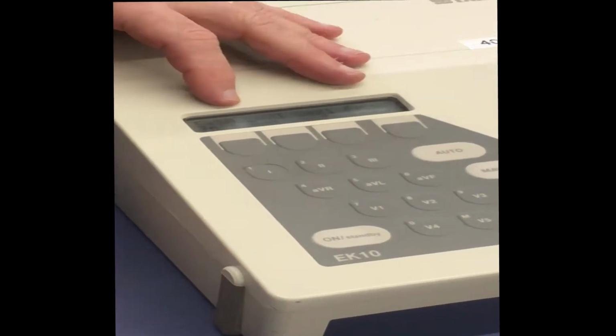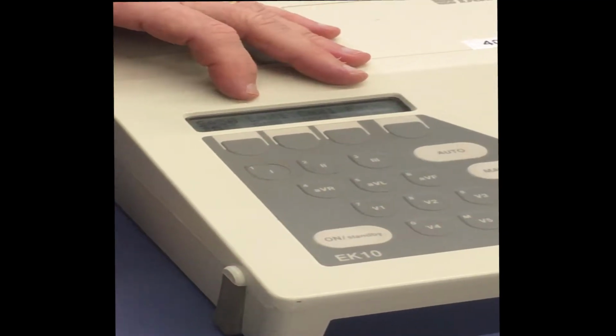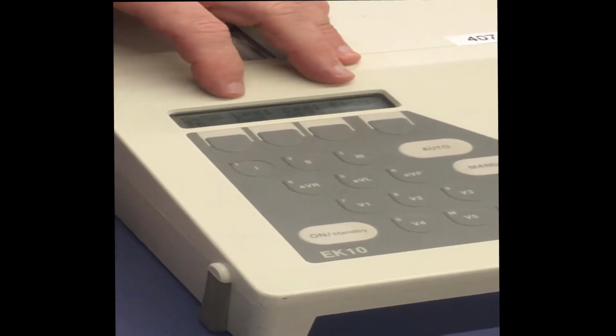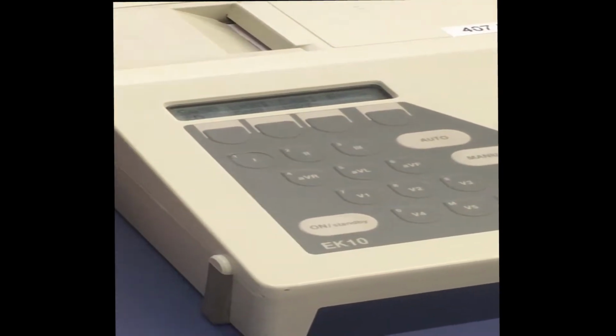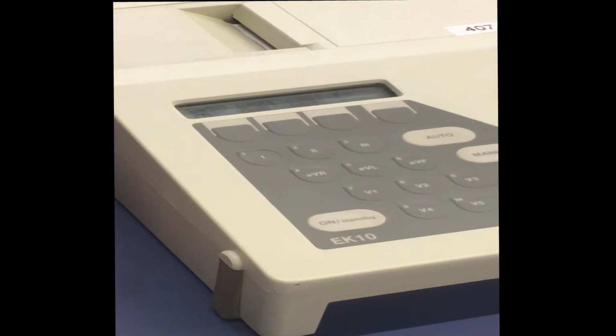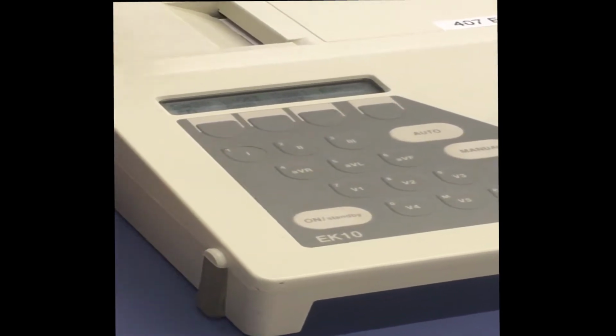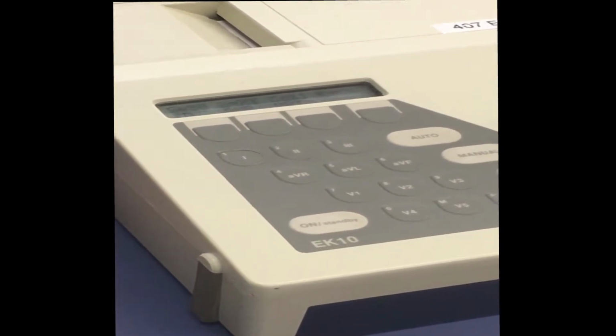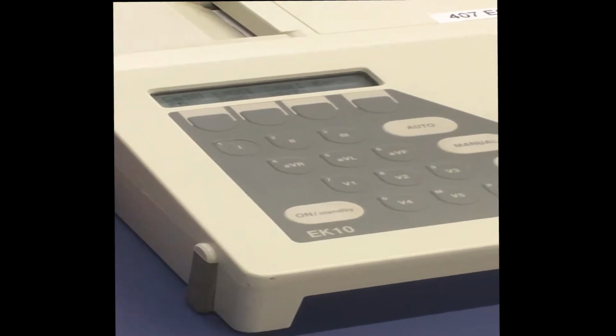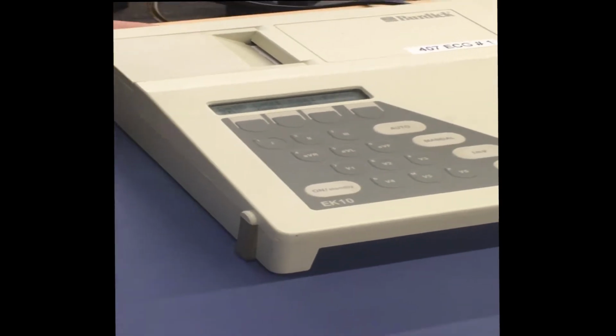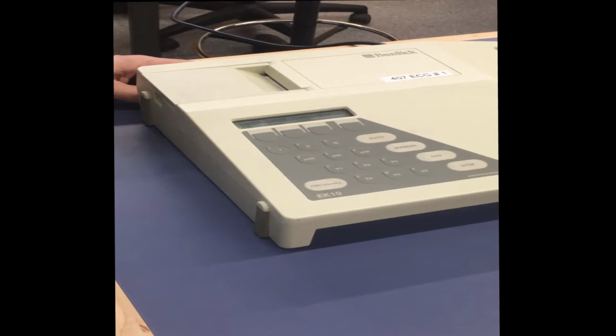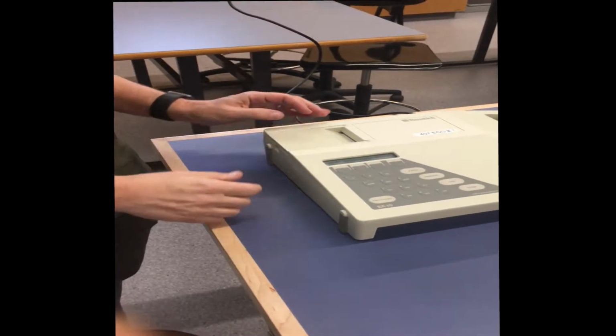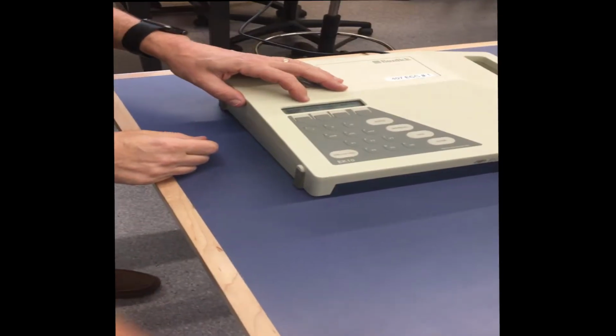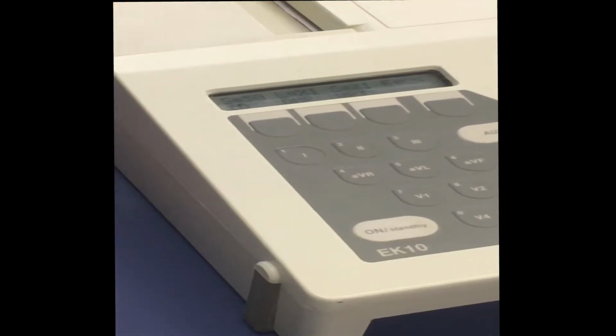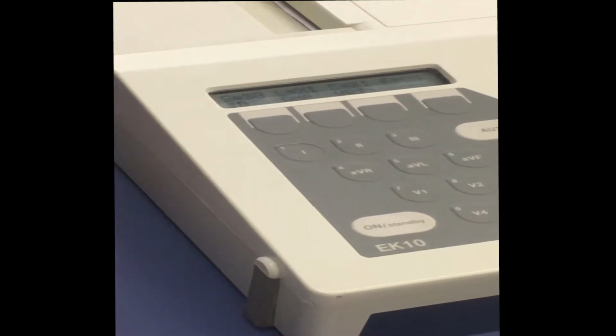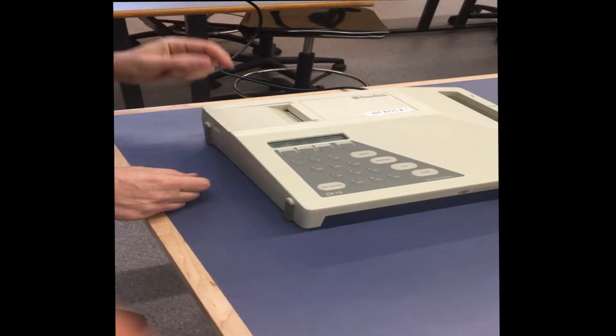The next number is the gain for the limbs, and so it says L is equal to X1. There are 3 different limb gains. It can either be H, which is a half, it can be 1, which is the normal, or it can be double the gain. So you have the ability to change the amplitude of the complexes. You can either half it, keep it at 1, or you can double it. So right now the limb is at 1. So if you found that your complexes were too big and going off the page, you would put it to half. If they were too small, you could double it.